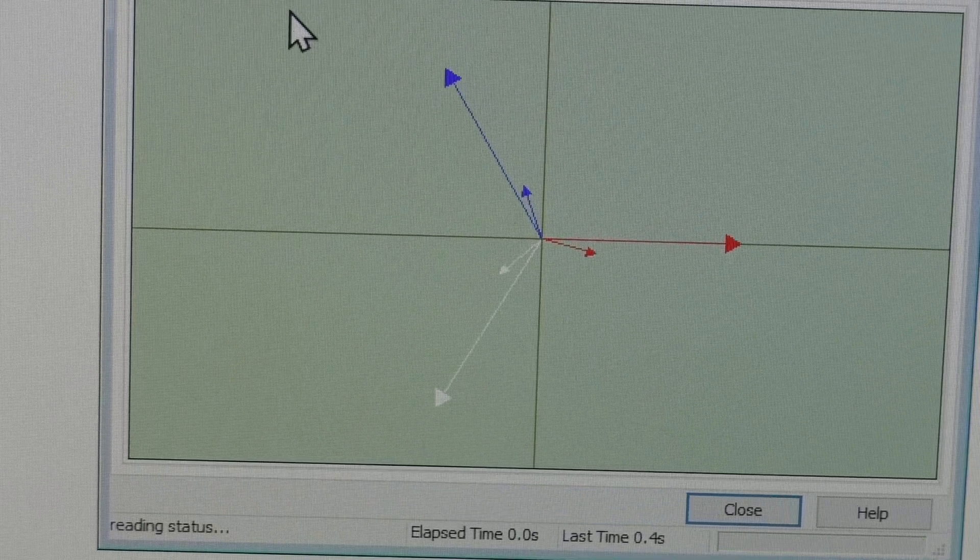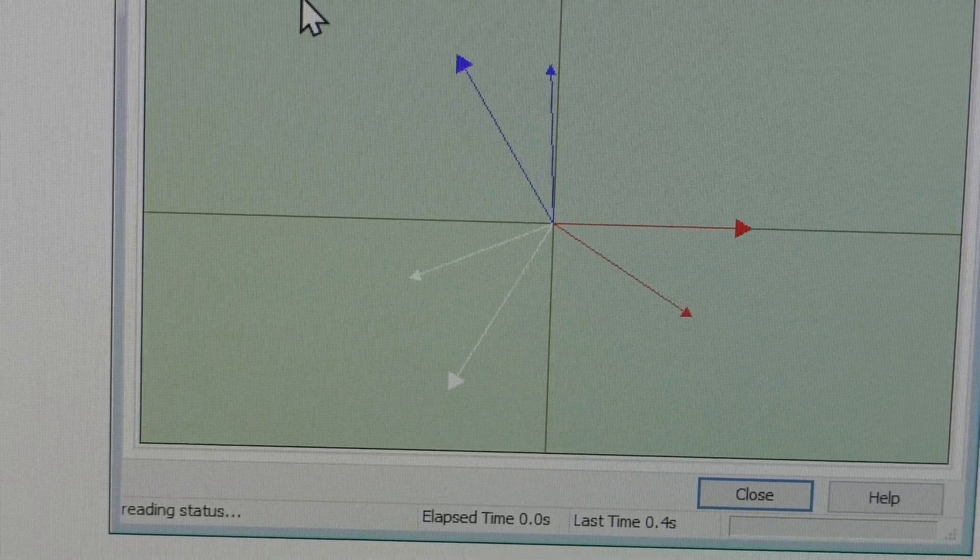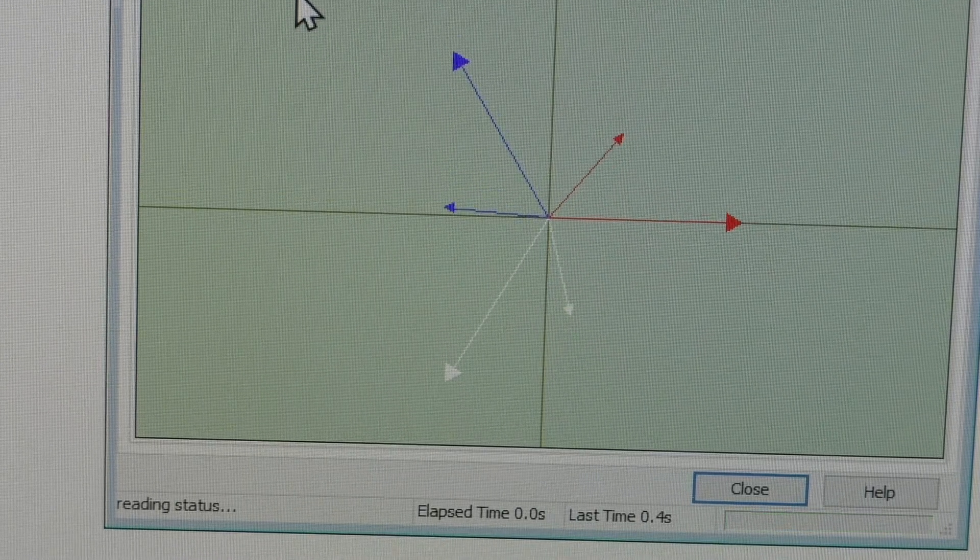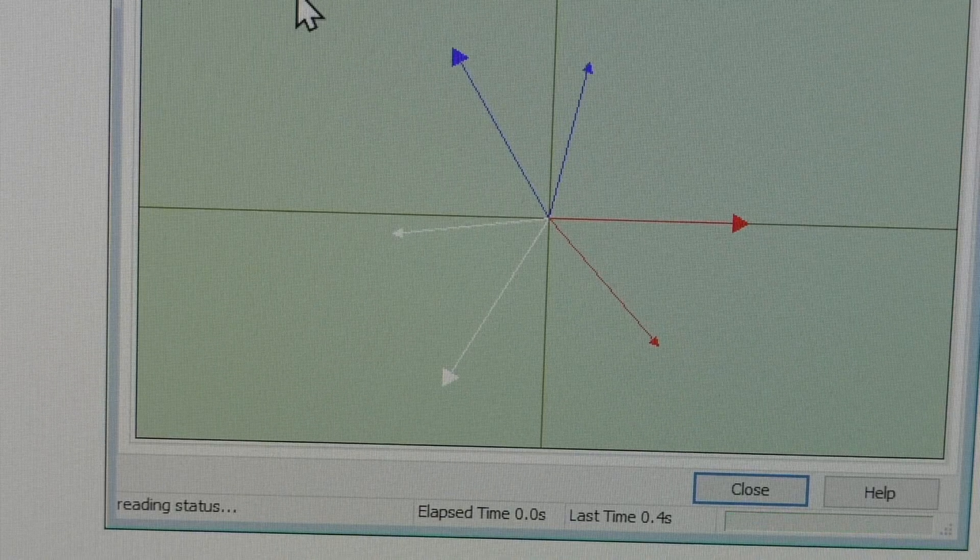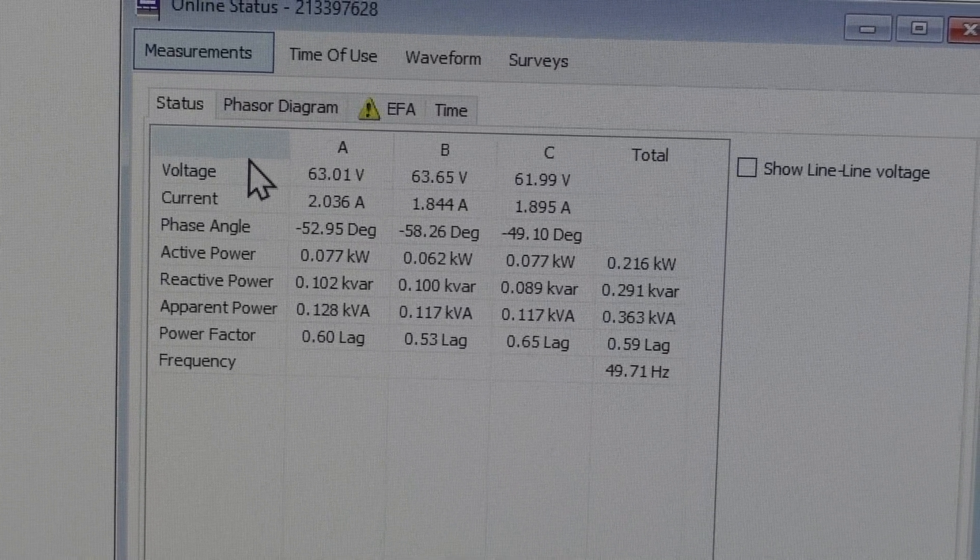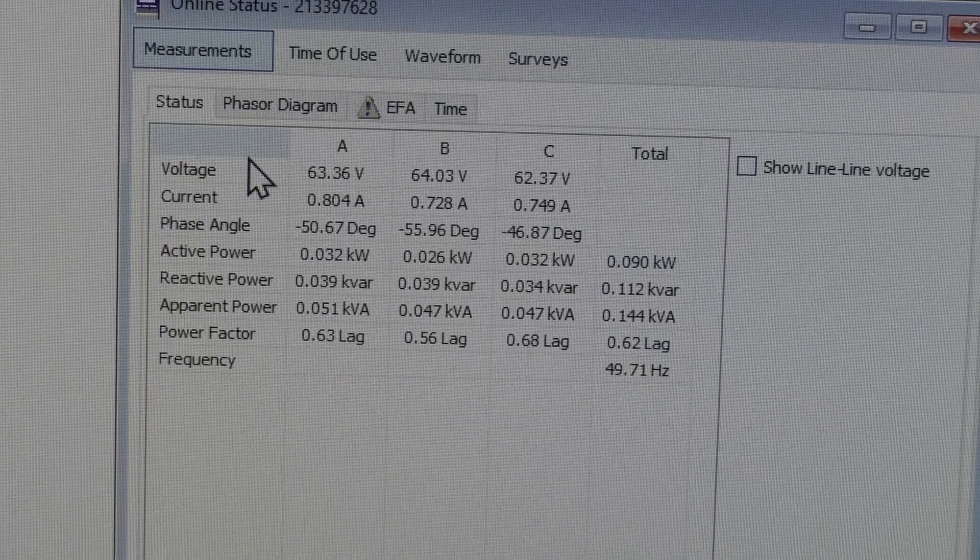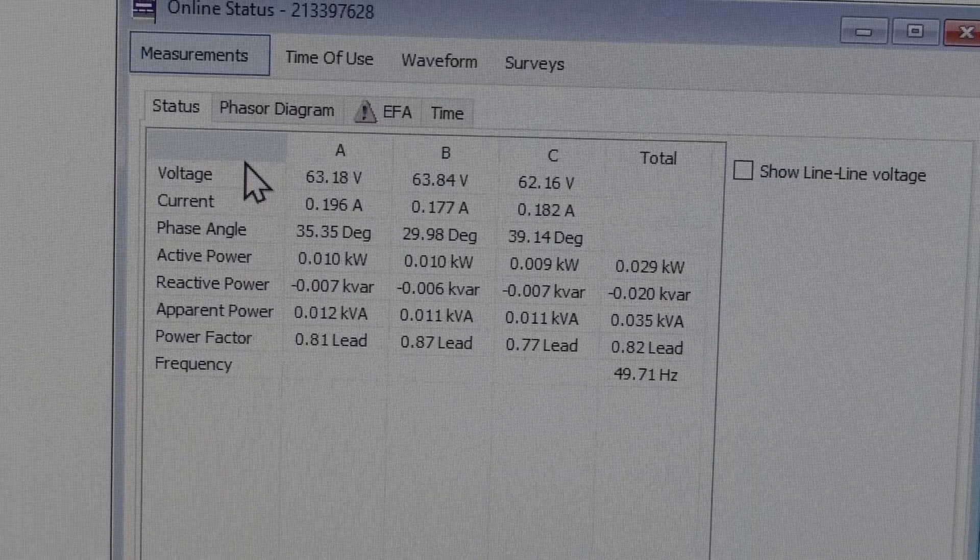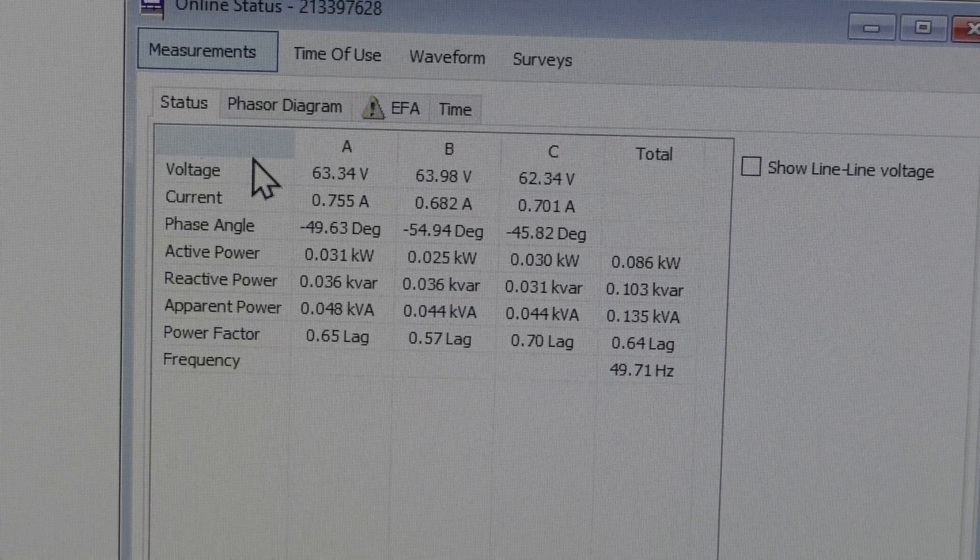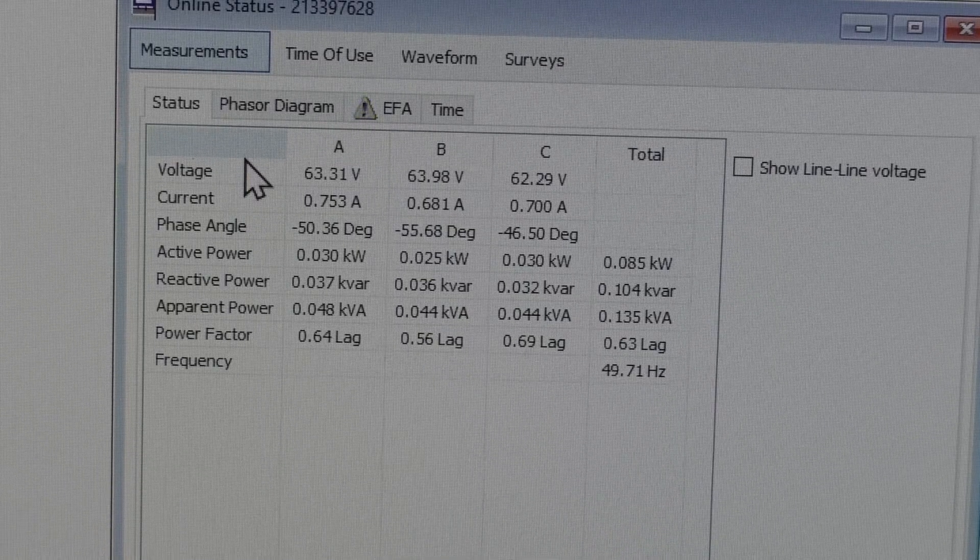This is the phase diagram. I'll go ahead and adjust some stuff, so we'll do amplitude and phase. You can see I can spin it right around. You can go right around. The only limit is I've got 180 degrees with one signal, so I need to create two to get the other. What I would do is use one signal in line with the volts and then have a 180 degree signal out to give me the current output.